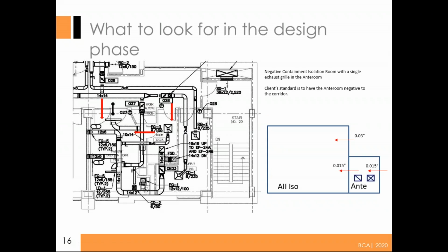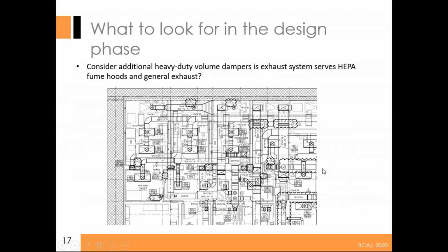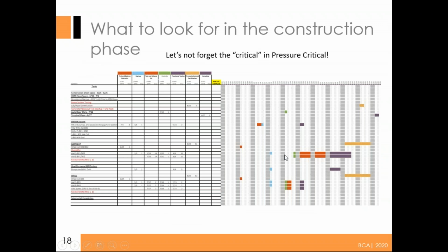One thing to do with a negative room, if you have a cascading negative pressure from a corridor to the room, you can make the ante room neutral by having a supply and return and using the negativeness of the isolation room to pull all of it through. So, back to the criticalness.